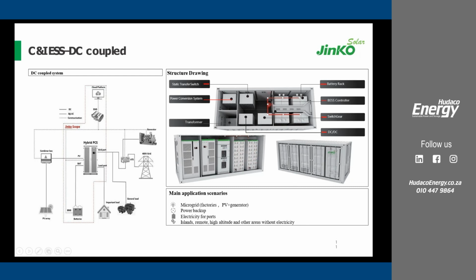Then on the other side, assuming a system with only grid, in the PCS, for 50, 100, and 150 kilowatts, we usually have four MCCBs. There are 4 breakers: one for PV, one for battery, one for load, and one for AC input. We usually call it the grid port. I'm just trying to create some memory so that you can see the breakers: one for battery, one for PV, one for load, and one for grid. The grid port is where we connect our grid or generator.